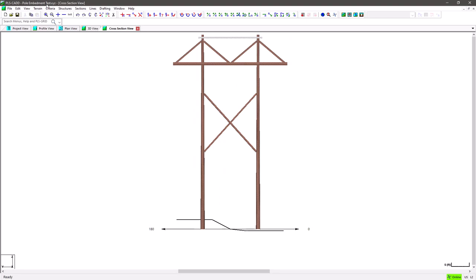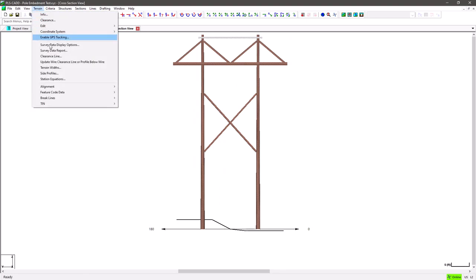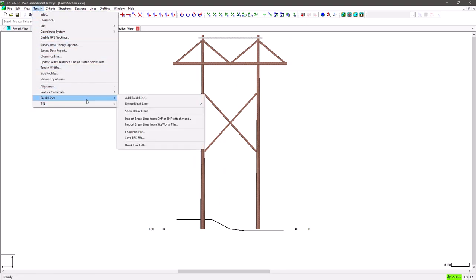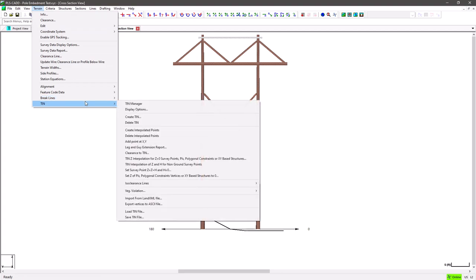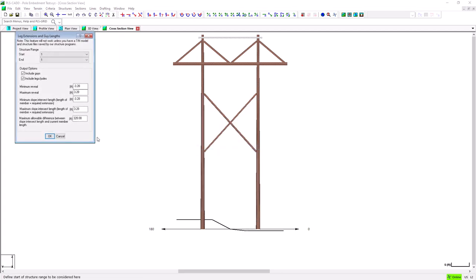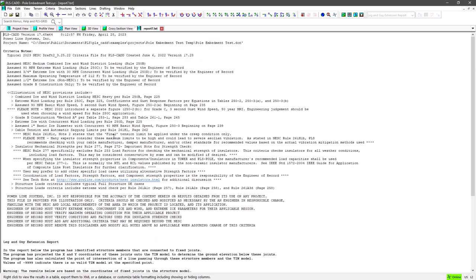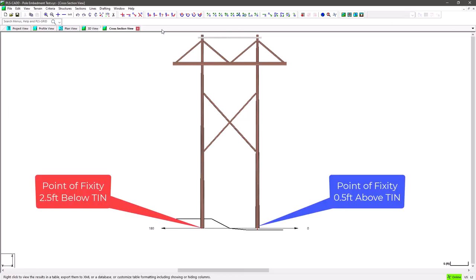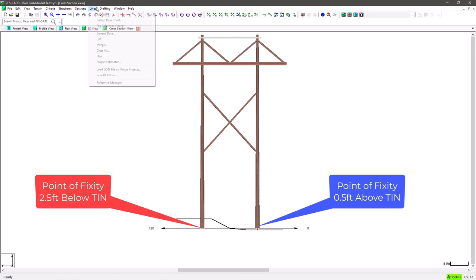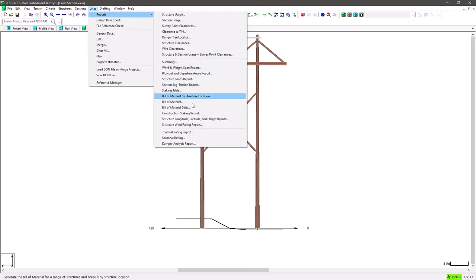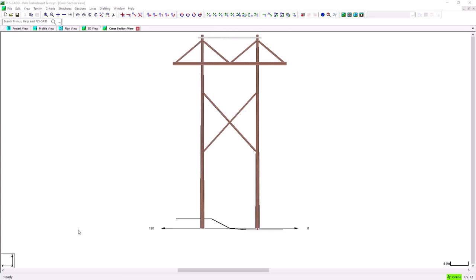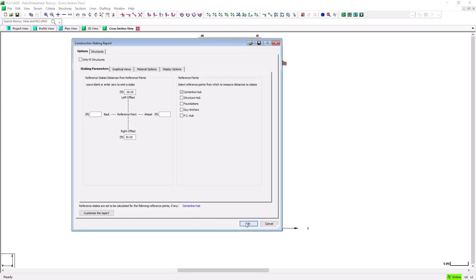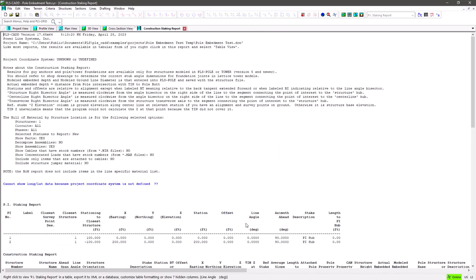Let's start by actually running a different report first to see where the poles currently sit. I'll navigate to Terrain, Tin, Leg and Guy Extension Report. And when we look at the results for this report and just focus on this column, we can see the additional length needed for the poles to intersect the tin surface are negative 2.5 and positive 0.5 feet. This means the left pole has its point of fixity below the tin surface and the right pole has its point of fixity above.